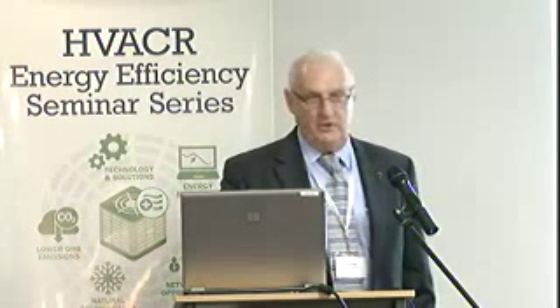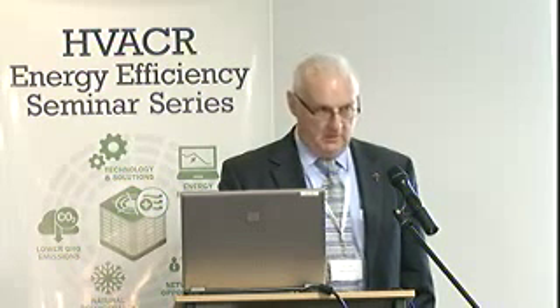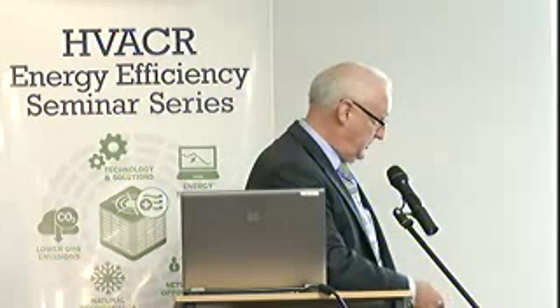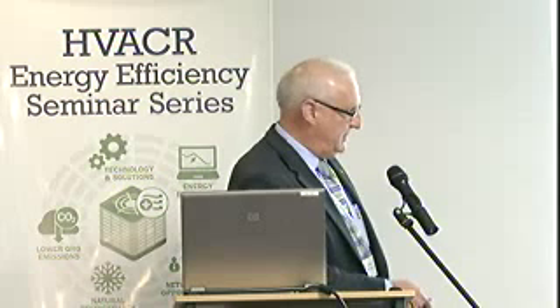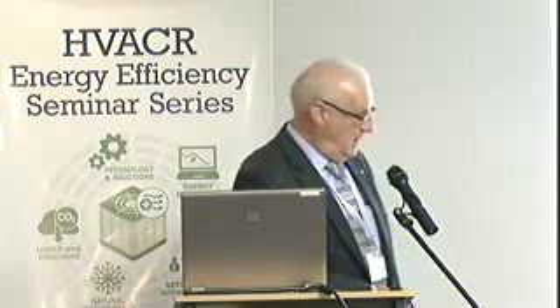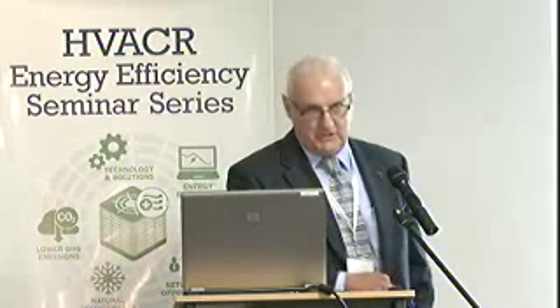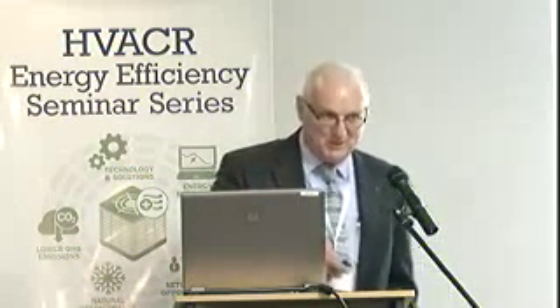And to that point, I thought I'd throw up a slide just to show the way that the two devices can be connected on your main switchboard. So here you'll see the VPO is in line with the main switchboard and all the loads. So all of the power, all the current is going through the device. Power factor correction device is installed down here, but controlled via the CTs after the meter. So it's a parallel device. It's not having all the current go through it. It's adjusting the voltage. Well, we'll get into what it's doing in a moment.